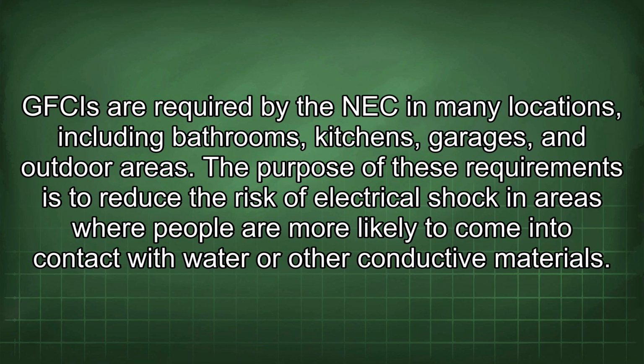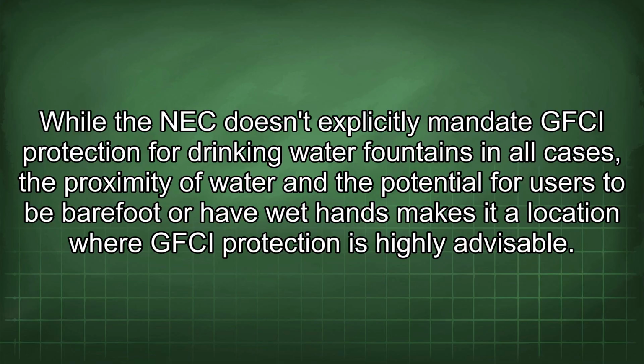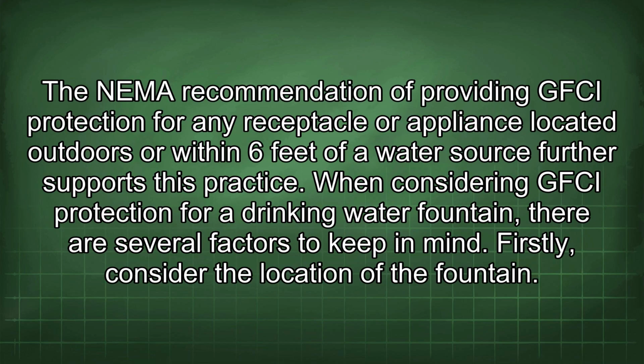GFCIs are required by the NEC in many locations, including bathrooms, kitchens, garages, and outdoor areas. The purpose of these requirements is to reduce the risk of electrical shock in areas where people are more likely to come into contact with water or other conductive materials. While the NEC doesn't explicitly mandate GFCI protection for drinking water fountains in all cases, the proximity of water and the potential for users to be barefoot or have wet hands makes it a location where GFCI protection is highly advisable. The NEMA recommendation of providing GFCI protection for any receptacle or appliance located outdoors or within 6 feet of a water source further supports this practice.